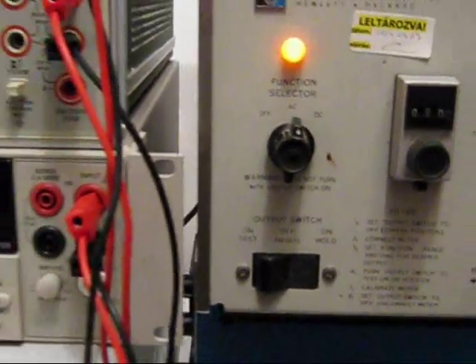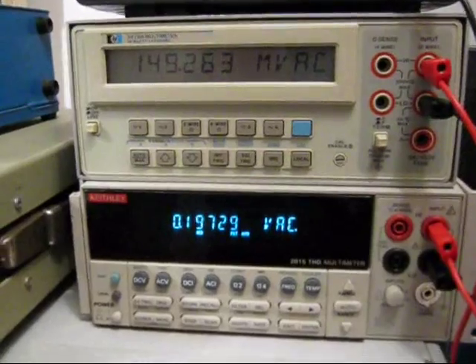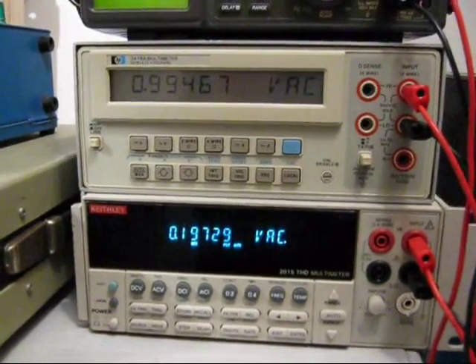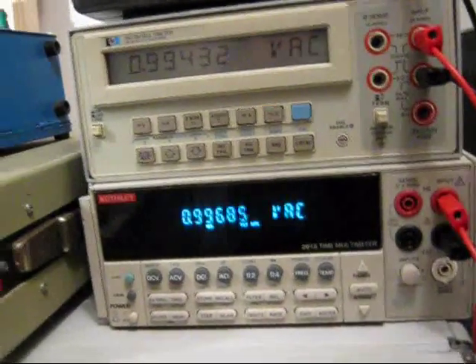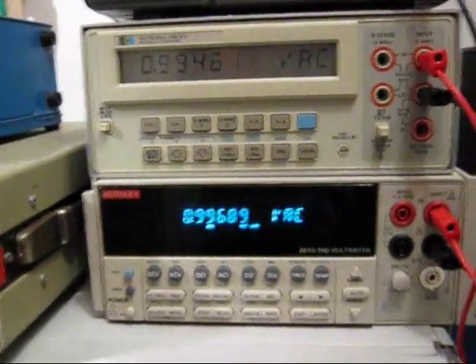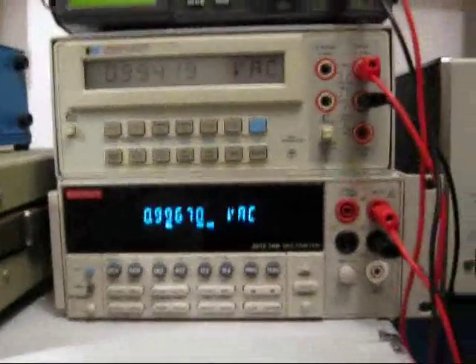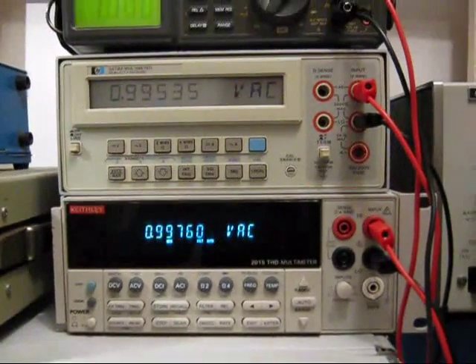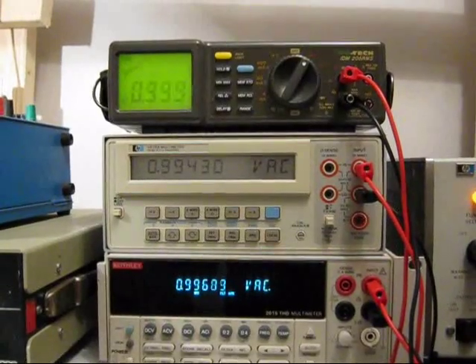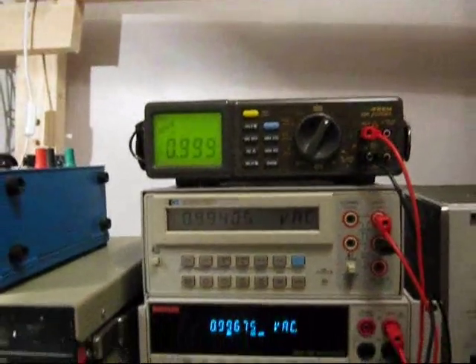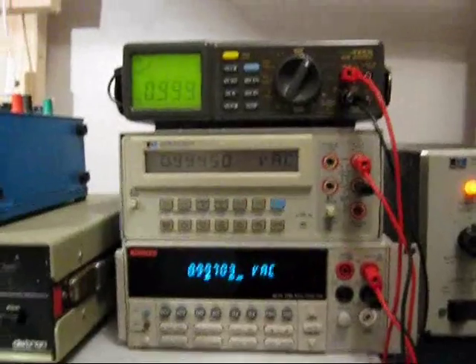I've now turned the calibrator to AC volts, and I've gone back to the 1 volt range. If I turn it on, then everything wakes up. And the Keithley shows 0.997 volts, and the HP shows 0.994 volts, and the Isotec showing 0.999.